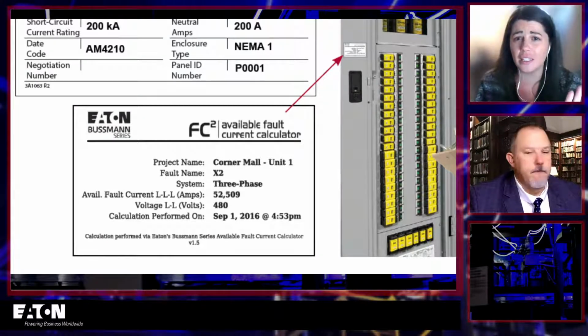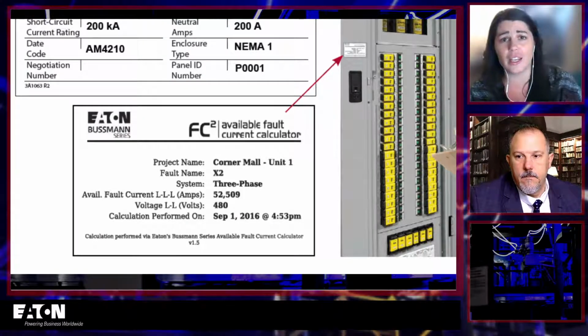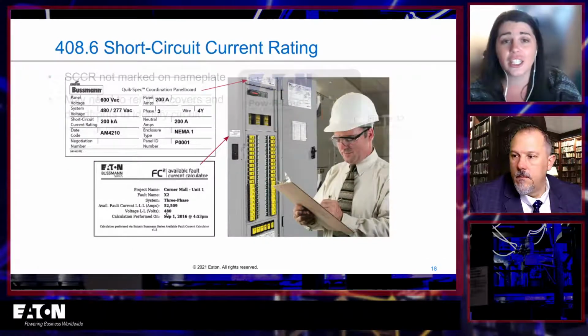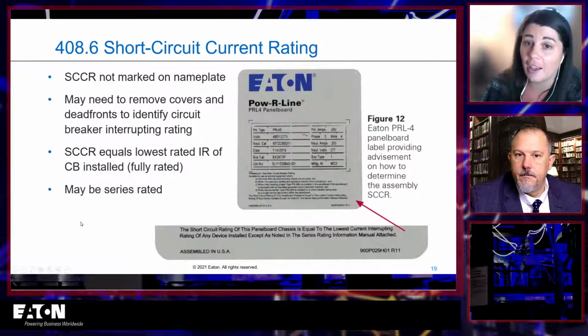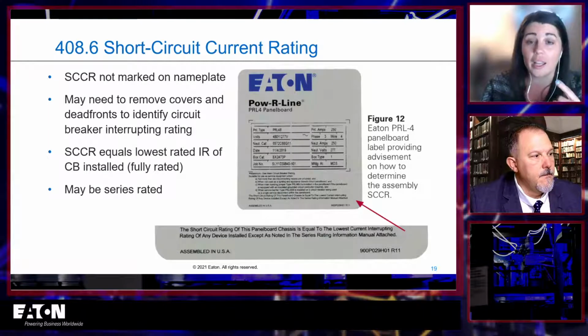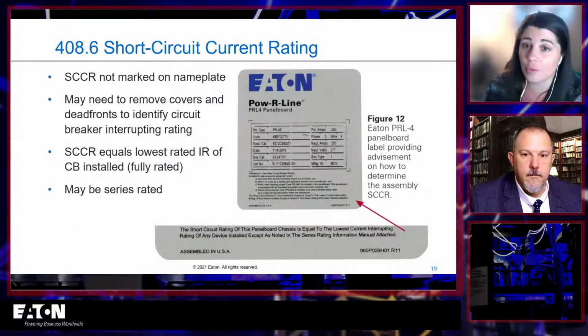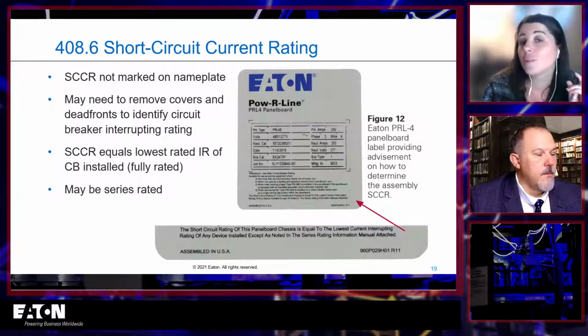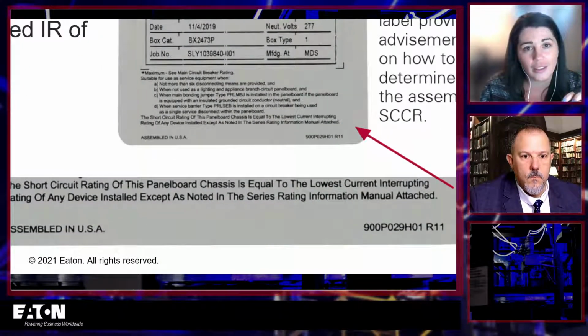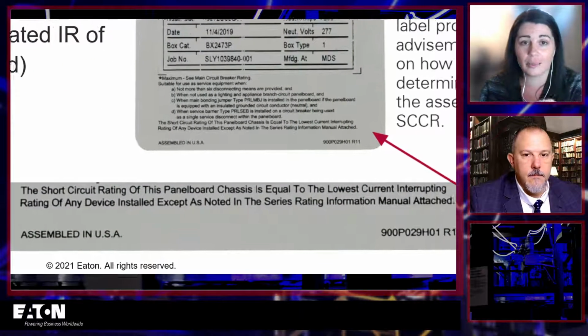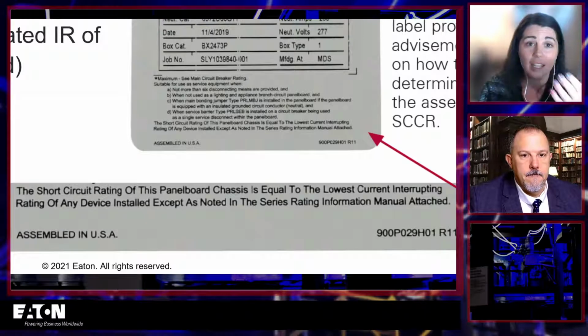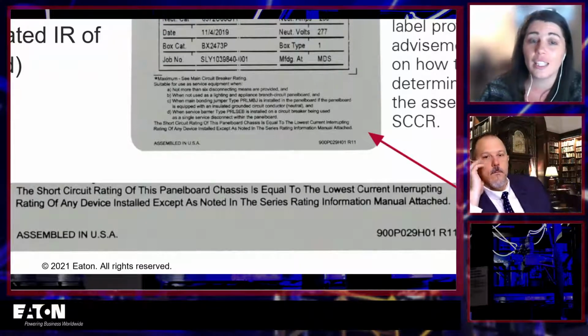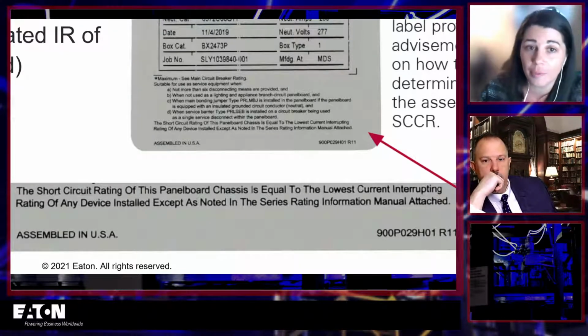So this is sort of the easy version, ideal version. If you go to the next slide, you'll see it actually can get a lot trickier if you have a breaker panel board or switchboard. And that's because you look at a breaker panel board or switchboard, and the SCCR is probably not actually marked on the nameplate. Instead, you get this paragraph.